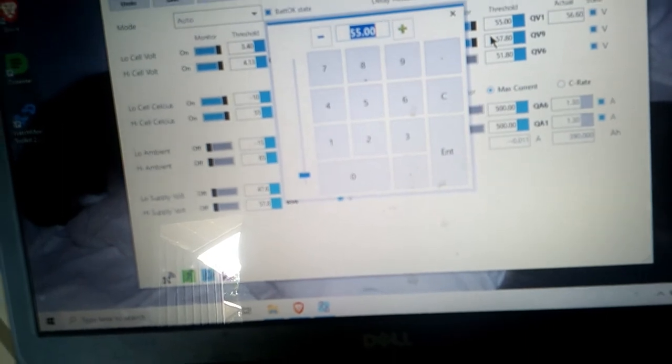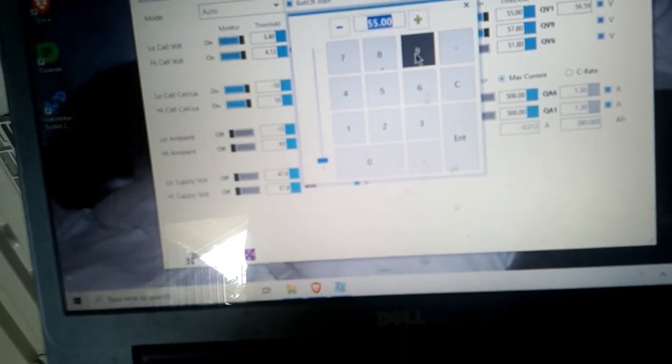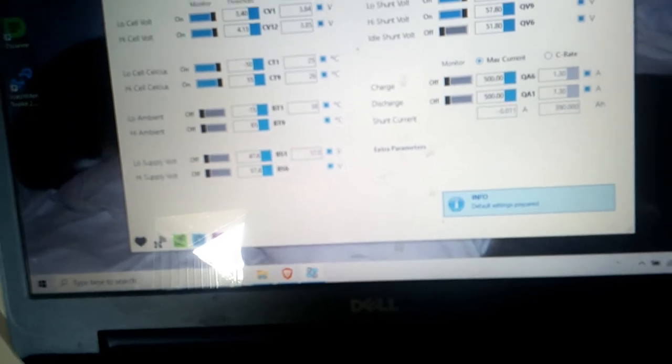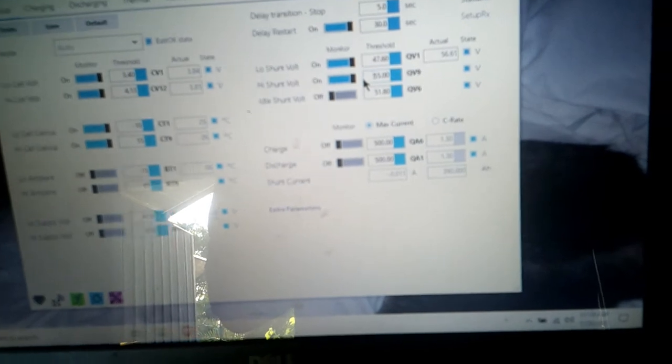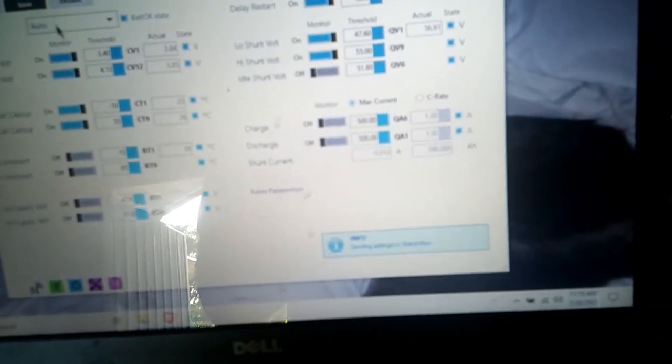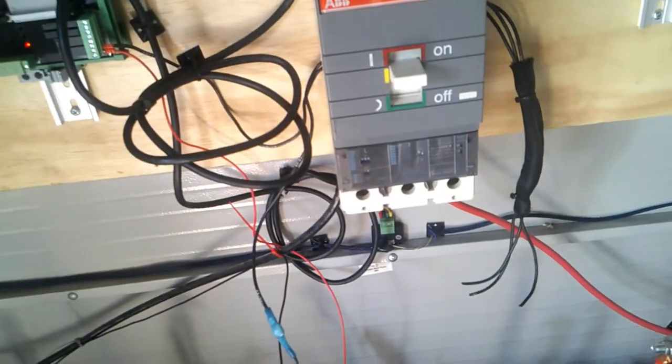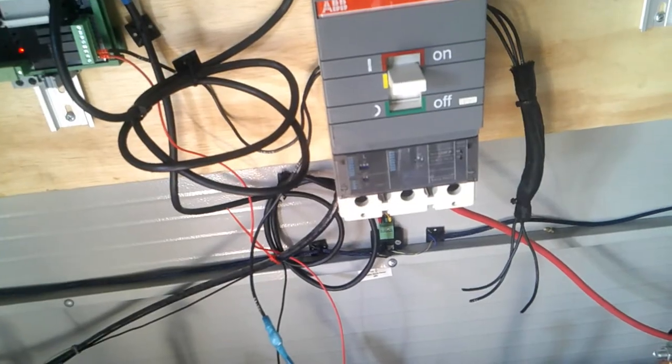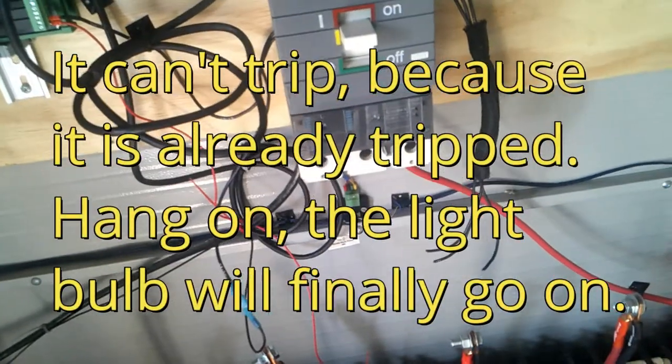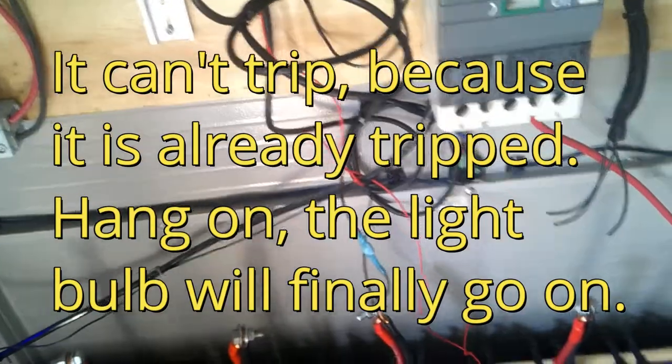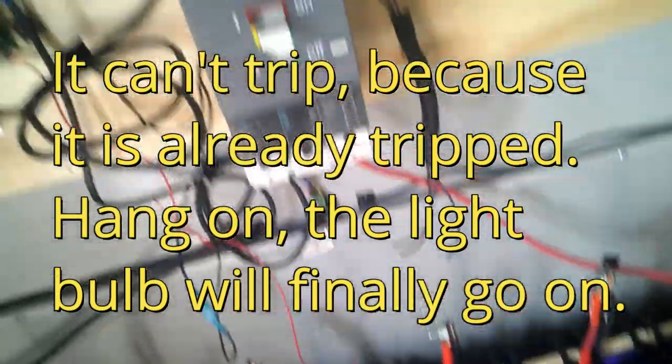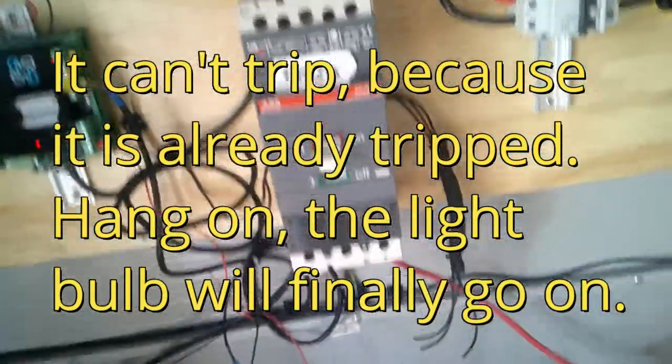Edit. High shunt. We'll do low shunt. Low shunt voltage is set... what, low shunt voltage is 55, that can't be correct. Okay so let me go to default. This software is a little wonky but it's pretty good. 46.5, let's go to high shunt voltage at 55, enter it. That should go into fault because it's actually above that. So if I go to save, that goes into a fault, that should cause the relay to trip and that should make that pop. But it does not.